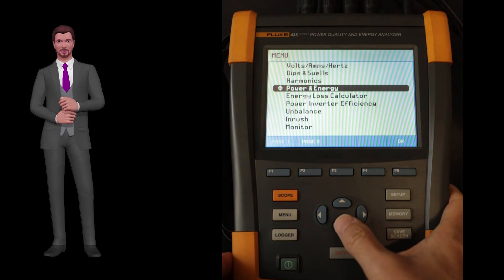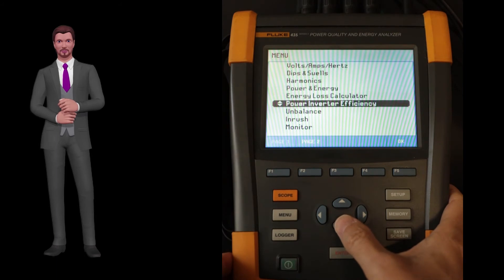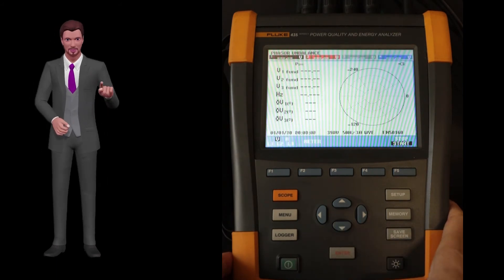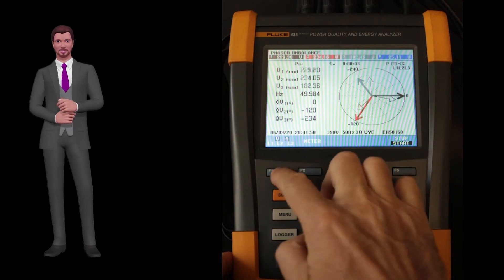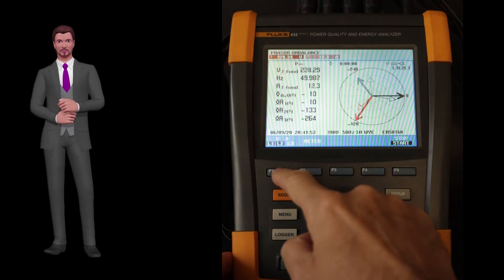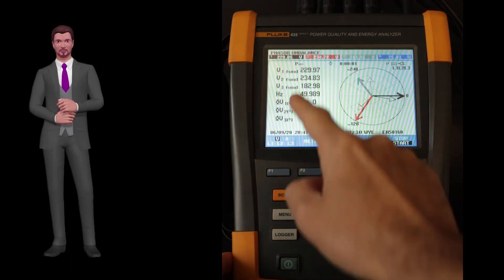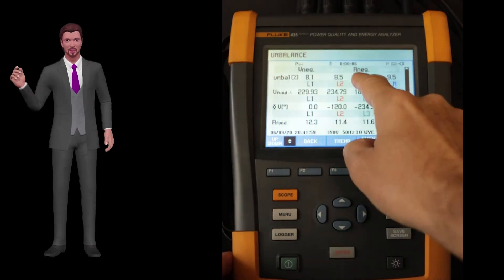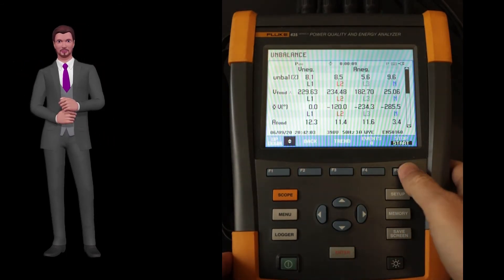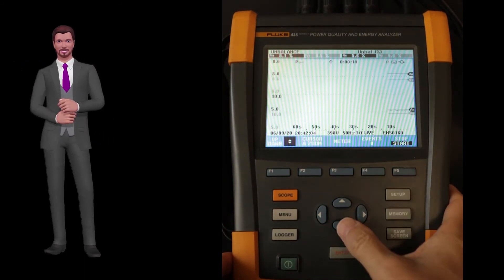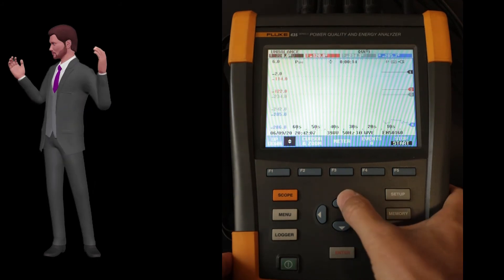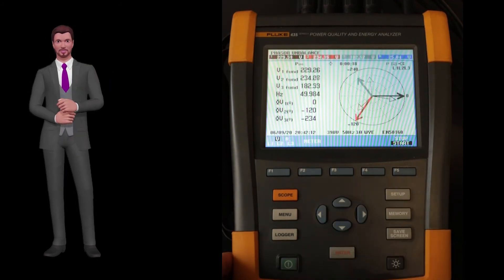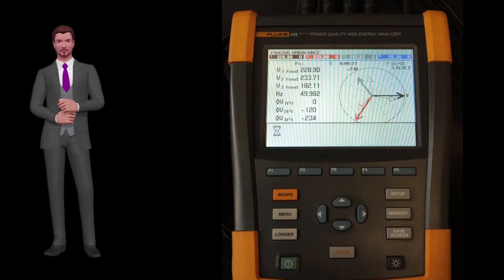The next function is the unbalance function, which, as its name indicates, allows you to measure and record voltage and current unbalances. Here, we can also see the phasor diagram with fundamental effective values and phase shifts for voltages and currents. In this case we have two important parameters: the negative and zero component percentages that tell us how big the unbalance is in the installation.